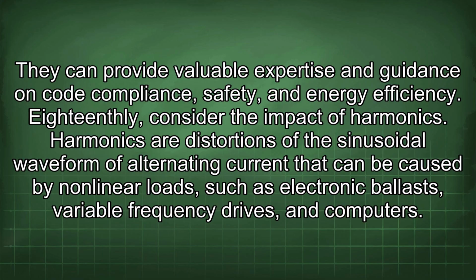Eighteenthly, consider the impact of harmonics. Harmonics are distortions of the sinusoidal waveform of alternating current that can be caused by nonlinear loads, such as electronic ballasts, variable frequency drives, and computers.